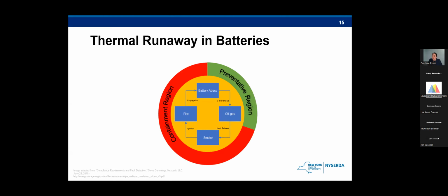So when it comes to lithium-ion batteries, thermal runaway is one of the primary risks to be alerted of. Thermal runaway is a reaction in which the lithium-ion cell enters an uncontrollable self-heating state. This can result in off-gassing, high temperatures, smoke, or fire, as you can see on the screen.